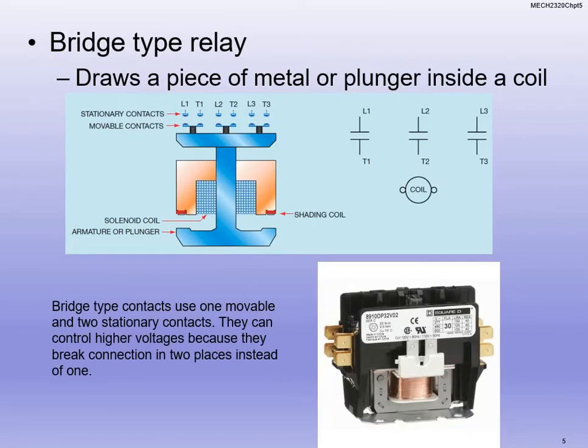We have other types of relays that can handle larger voltages. This is a bridge-type relay — it looks more like our motor contactors. The solenoid actually closes an entire plunger, and that entire plunger handles multiple contactors at once. This is how we handle different lines of three-phase motor power, as opposed to control logic.